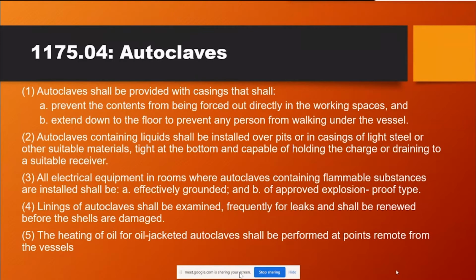Autoclaves containing liquids shall be contained over pits or in casings of light steel or other suitable materials, tight at the bottom and capable of holding the charge or draining to a suitable receiver. All electrical equipment in rooms where autoclaves containing flammable substances are installed shall be effectively grounded and of approved explosion-proof type. Ayan. Linings of autoclaves shall be examined frequently for leaks and shall be renewed before the shells are damaged. The heating of oil for oil jacket autoclaves shall be performed at points remote from the vessels.